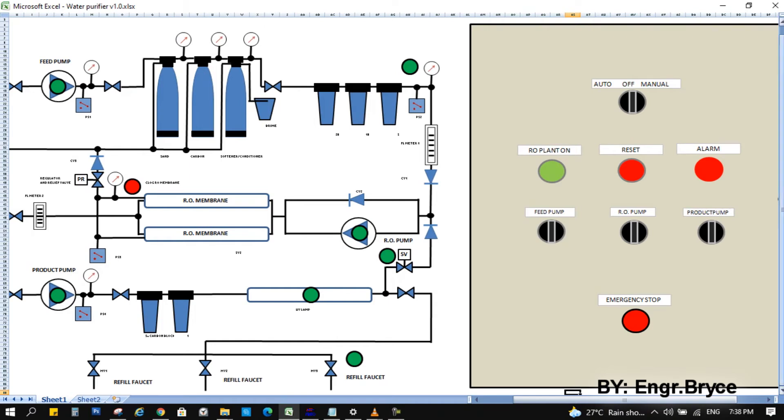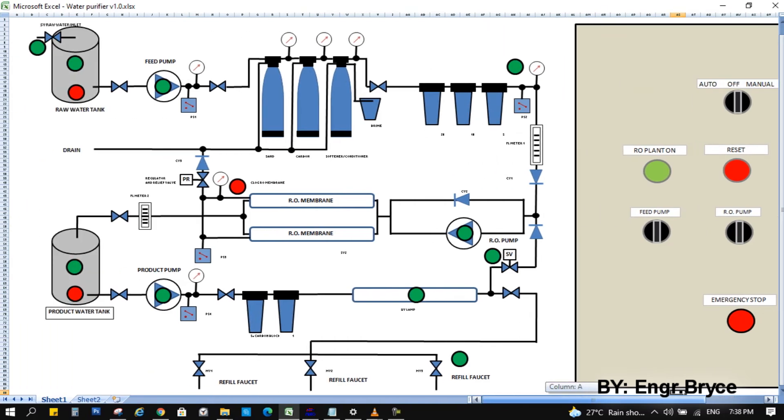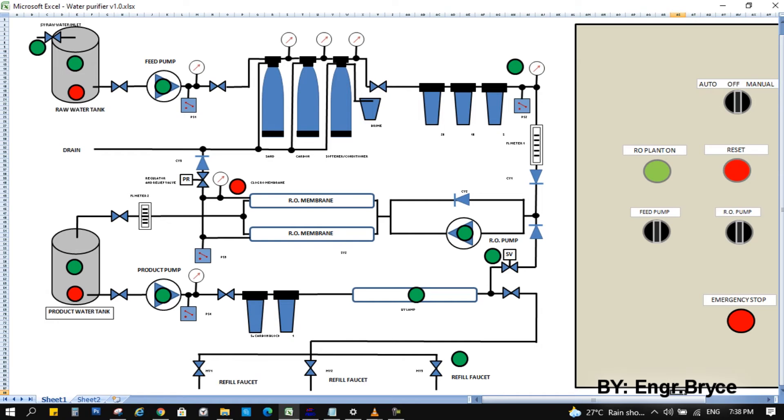For manual mode, it has three switches to turn on and off the feed pump, the RO pump, and the product pump. For automatic mode, the feed pump start only if tank 1 is not empty and no existing alarm. And the pump stop if high pressure in the output line, tank 1 is empty, and RO plant alarm.